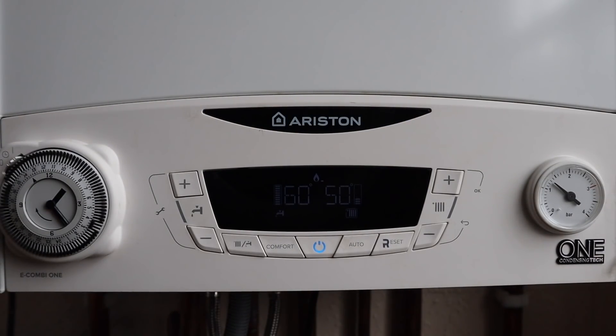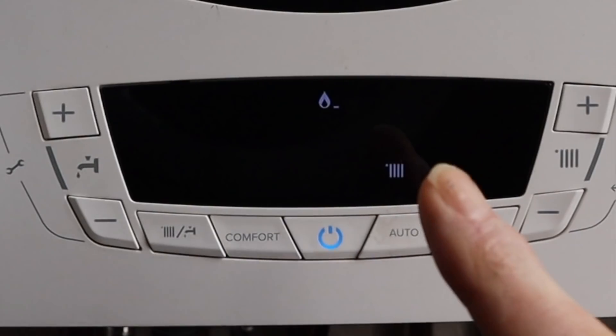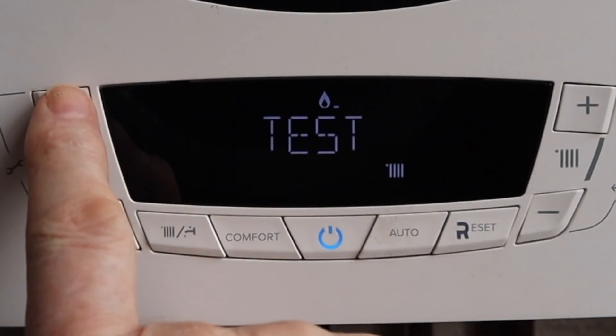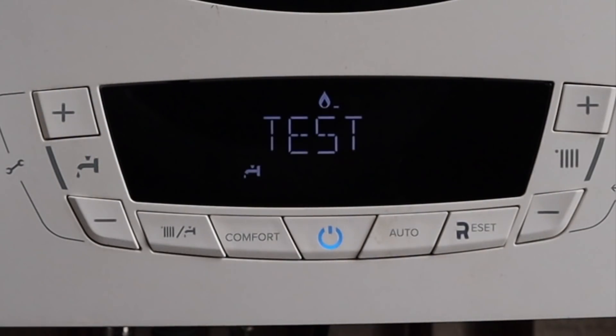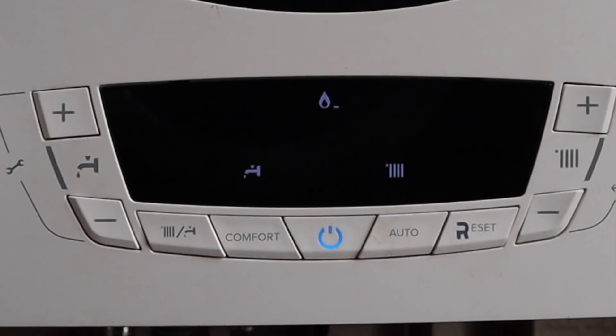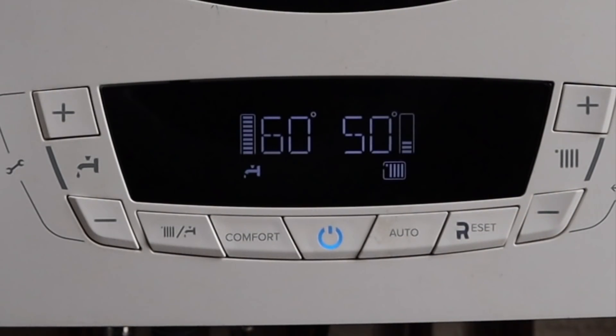This is how you put the Ariston E Combi 1 into service mode. Press and hold the reset button until 'test' comes up. A radiator symbol appears — that's maximum setting for central heating only, which we don't want. Press the plus button and the tap symbol comes on — that's maximum rate for hot water, which we do want. Press the minus button with both the tap and radiator symbol showing, and that puts us into minimum setting. To exit, press and hold the reset button.